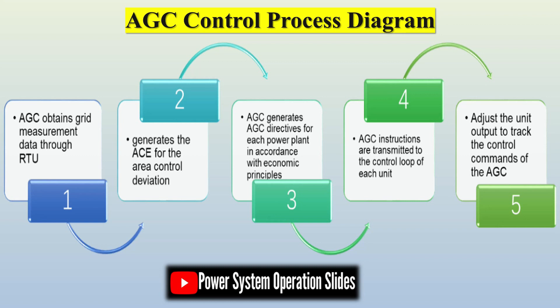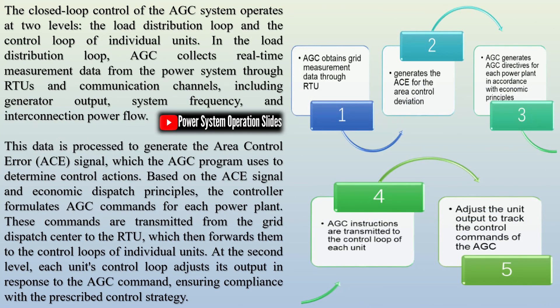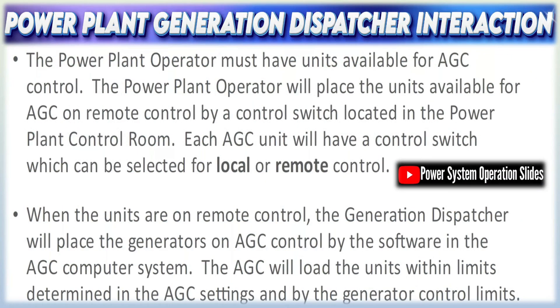ACE is computed as the combination of two components: the difference between actual and scheduled net power interchange (i.e., difference in the tie-line flows), and a term proportional to the frequency deviation from nominal, often weighted by a frequency bias factor. The AGC's goal is to drive A.C.E. to zero, ensuring both proper power exchanges and stable frequency. ACE is central to how AGC operates: positive A.C.E. indicates that the area is over-generated or exporting more power than scheduled along with a possible frequency rise.